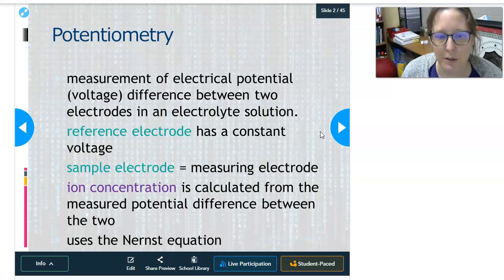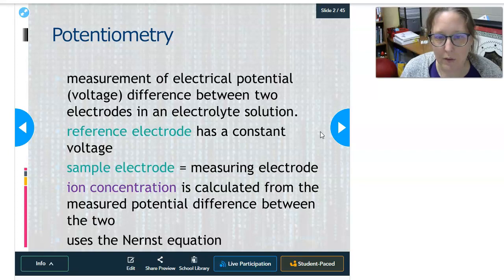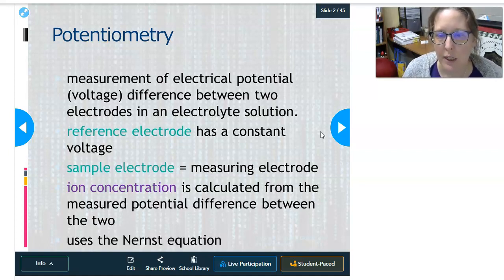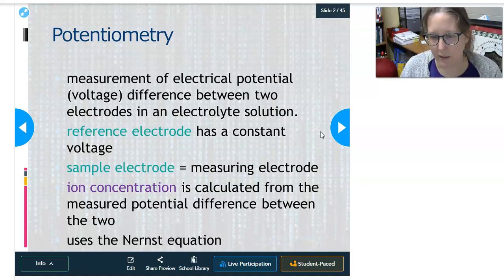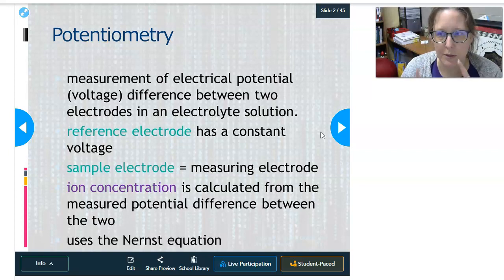Potentiometry is a measurement of the electrical potential or the voltage difference between two electrodes in an electrolyte solution. There is a reference electrode that has a constant voltage and a sample electrode, which is the measuring electrode, measuring the electrolytes in the sample. The ion concentration is calculated from the measurement of the potential difference between the two electrodes, and it uses the Nernst equation.